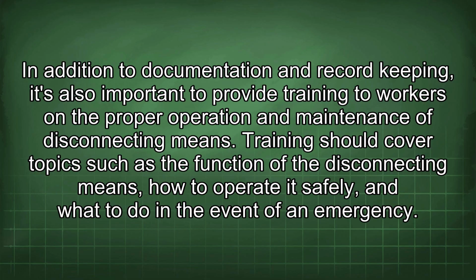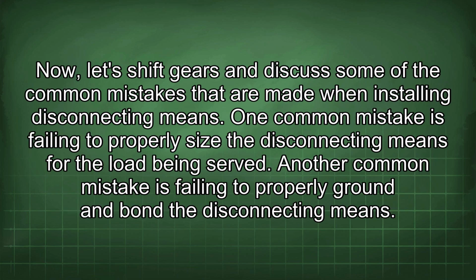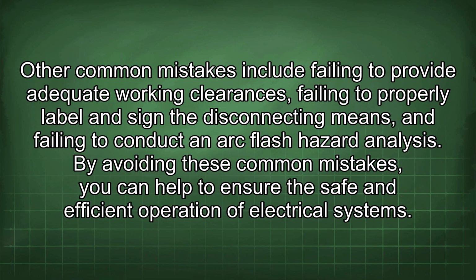In addition to documentation and record keeping, it's also important to provide training to workers on the proper operation and maintenance of disconnecting means. Training should cover topics such as the function of the disconnecting means, how to operate it safely, and what to do in the event of an emergency. Now let's shift gears and discuss some of the common mistakes that are made when installing disconnecting means. One common mistake is failing to properly size the disconnecting means for the load being served. Another common mistake is failing to properly ground and bond the disconnecting means. Other common mistakes include failing to provide adequate working clearances, failing to properly label and sign the disconnecting means, and failing to conduct an arc flash hazard analysis. By avoiding these common mistakes, you can help to ensure the safe and efficient operation of electrical systems.